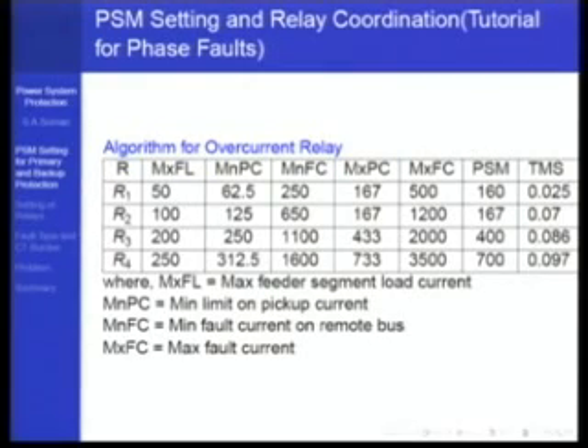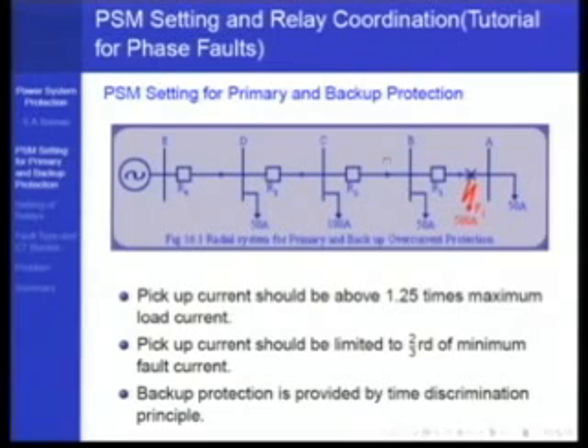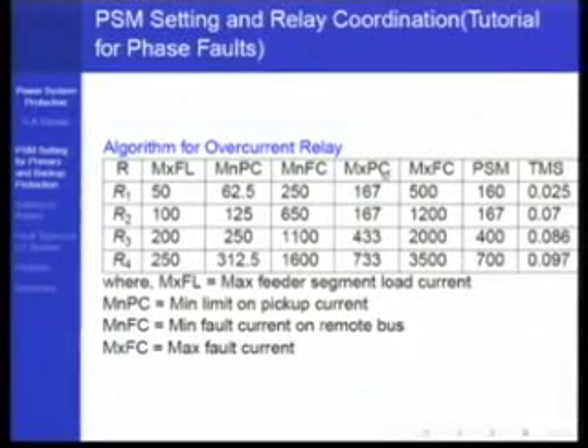It is 2/3 of 650 amperes. Why 2/3 of 650 amperes? Because this R3 is backing up R2, and the minimum fault current seen by R2 on its primary section is 650 amperes. So that current has to be protected. This has to back up the next section, and therefore it should detect a fault current of 650 amperes. Therefore 2/3 of 650, which is 433 amperes. So therefore the range is 250 to 433.